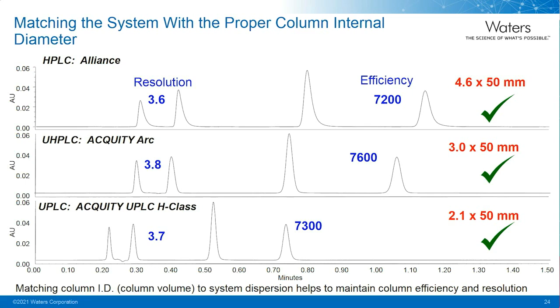We have categorized LC systems into 3 categories: HPLC, UHPLC, and UPLC. HPLC has a dispersion of 30 microliters or greater, UHPLC sits in the middle, and UPLC has a dispersion level less than 12 microliters. Due to these dispersion levels, we must appropriately match the right type of column size, volume, and particle size with the system dispersion to maximize column performance.